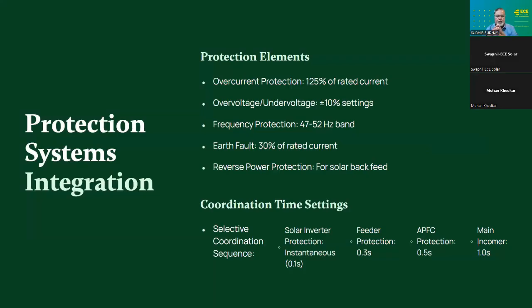Now let's talk of protection systems. You are all energy engineers, so I need not repeat it for you, but there are some solar participants also in this seminar, so let me give them a brief. Overcurrent protection has to be set at 125% of the rated current, and voltage at plus minus 10%. All relay settings must be plus minus 10%. Earth fault should be 30% of the rated current. And reverse power protection is required in case they are not going in for a net metering or net billing kind of arrangement.